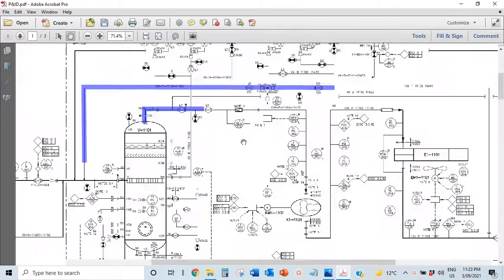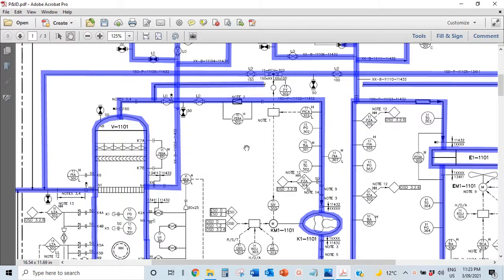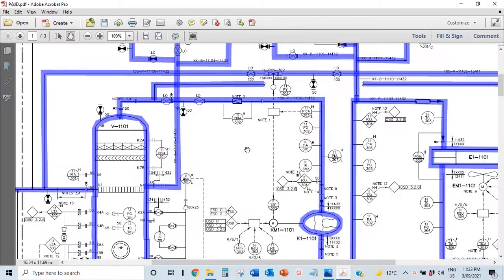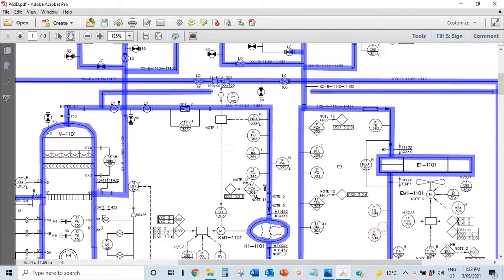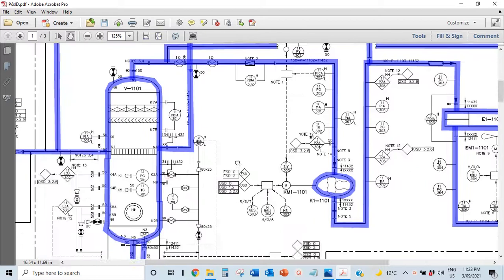Because when you put it into software like Fred or Fast, you want to calculate how quickly you would have your blowdown. When this blowdown opens, how long is it? How long is it going to be before the gas blows down to maybe 1 bar or 2 bar? Maybe you have gas here that's maybe 10 bar, although we know here it's much less than that. But you want to have an idea how long it would take, because you're going to do blowdown calculations with the software.